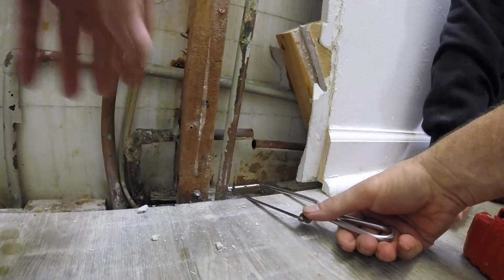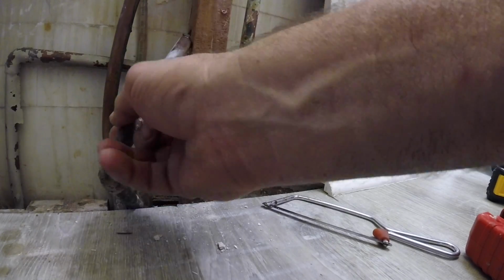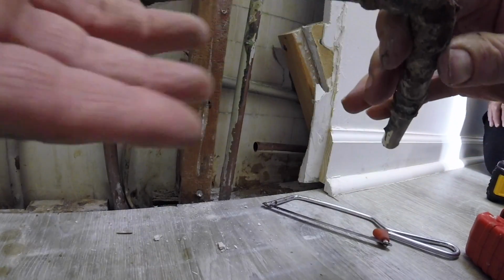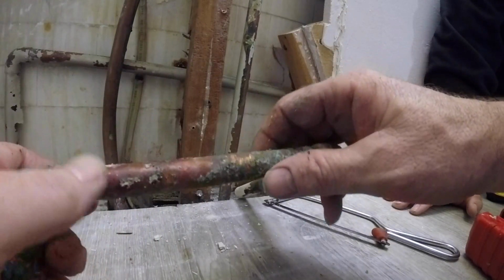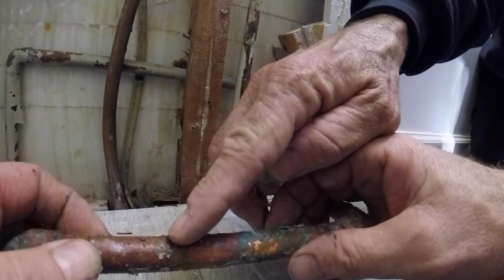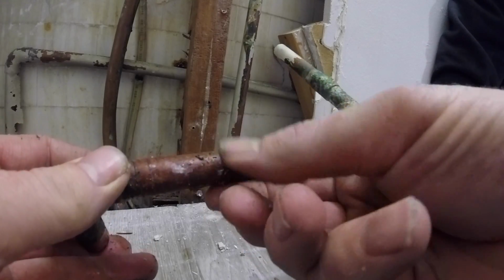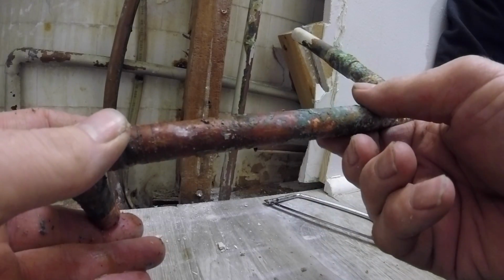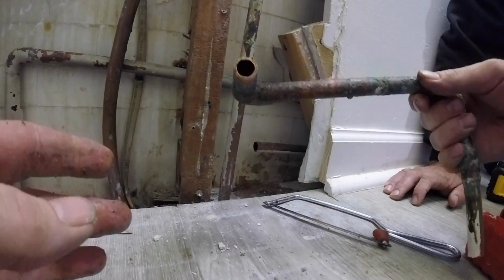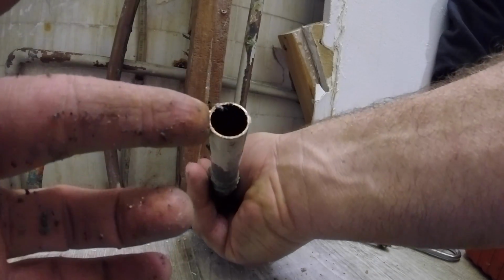Nice. That's something. Now, I want to get this out of here in one piece to reveal the leak. There it is. Where's that? See it there. Oh, here it is. Good eye. Right here is the leak. See where it wore against the pipe, the copper? That's it. Oh, that was thick copper right there. Yeah. Thick copper, cheap copper. There it is.